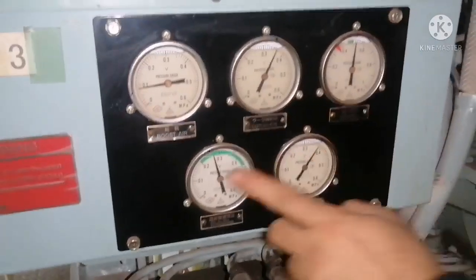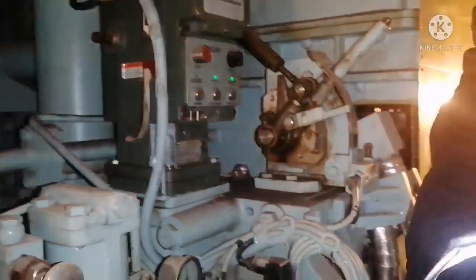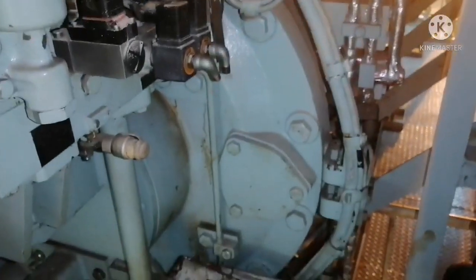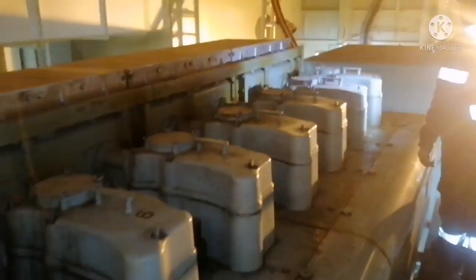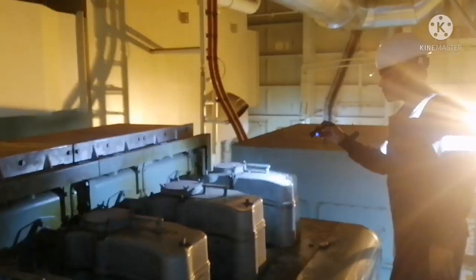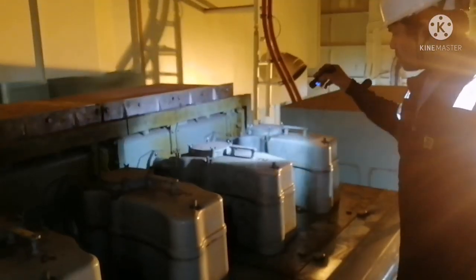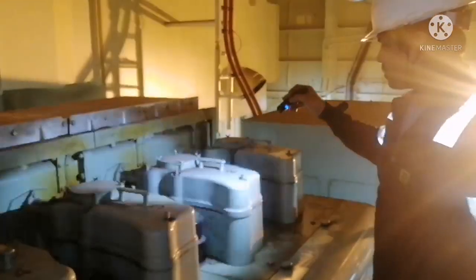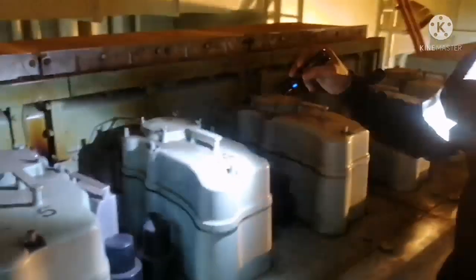So all should be within the marked range. If it is within the range, then it is okay. All you can see, the governor has a green light, that is, strength is okay. Just take a look over the cylinder head area, there should not be any abnormal leakages. Just check the local temperature, and you can see here I could find there are no abnormalities.